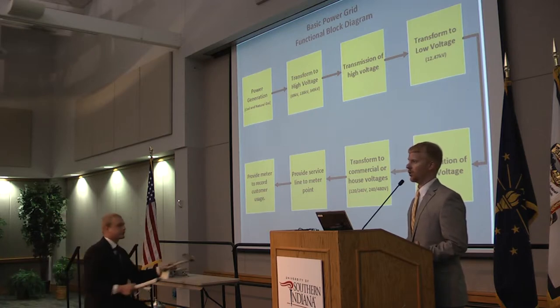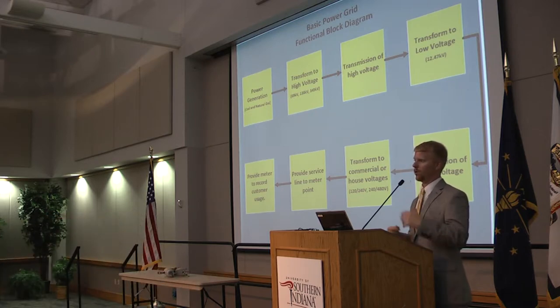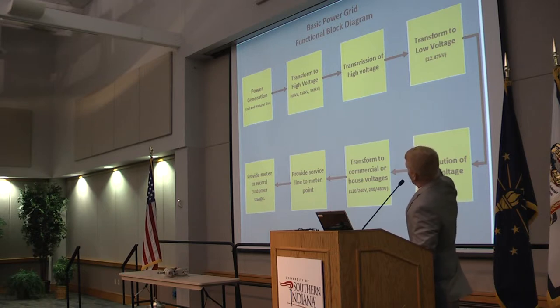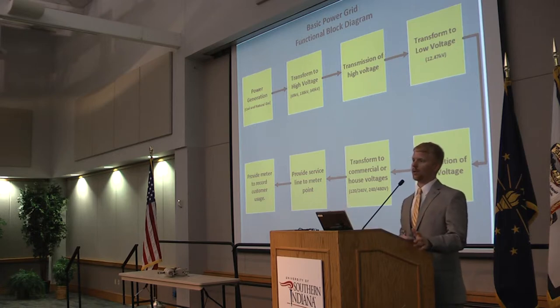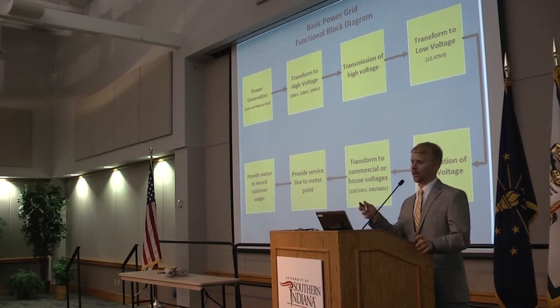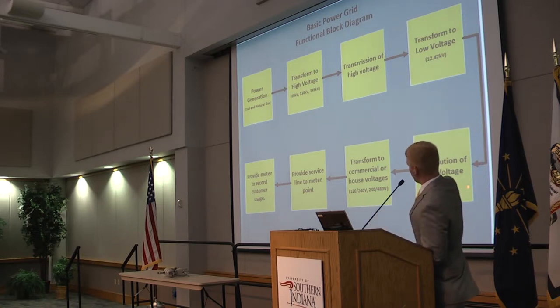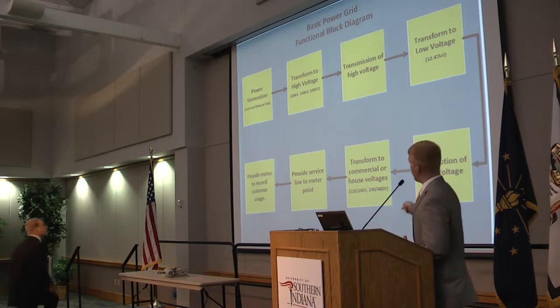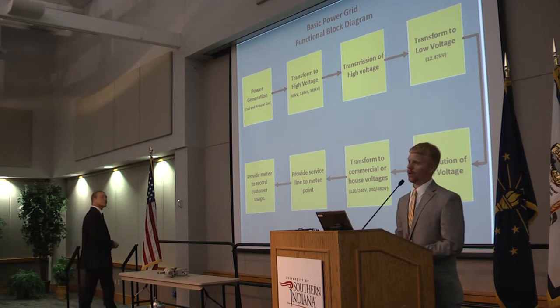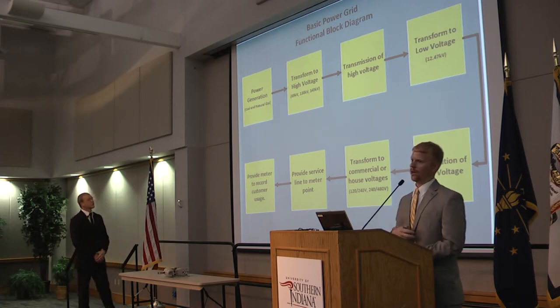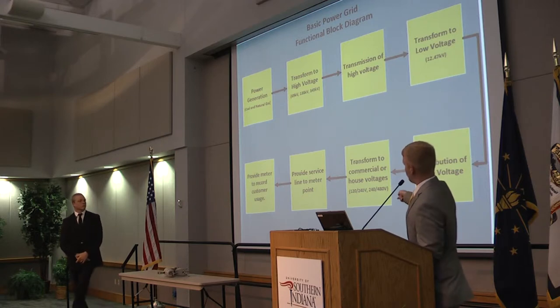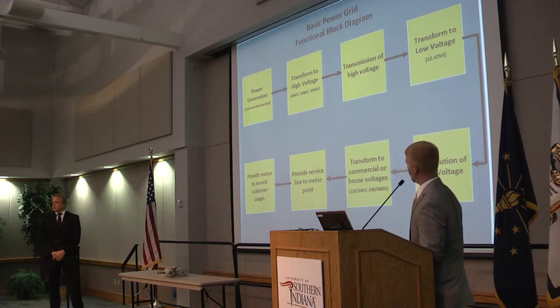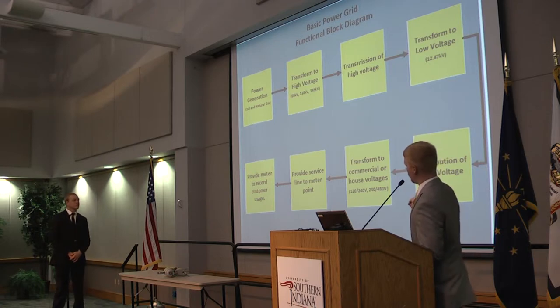It's a distribution substation where we transform from transmission voltage down to distribution voltage. The distribution voltage that we're dealing with is 12,470 volts. From the distribution voltage, we send out distribution lines, which are your most common lines that you see feeding down the road. This is the distribution voltage line that leads to the customer's house or wherever it is, where we put a pole-mounted or pad-mounted transformer that transforms the voltage down into a lower usable voltage, which is usually at house voltage is 120, 240, or a common commercial voltage is 240, 480 volt.